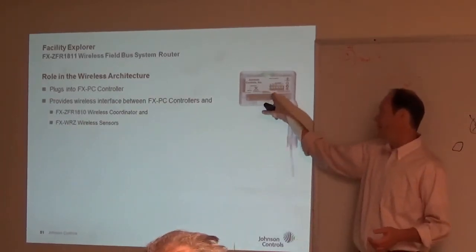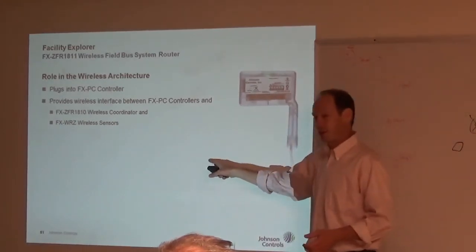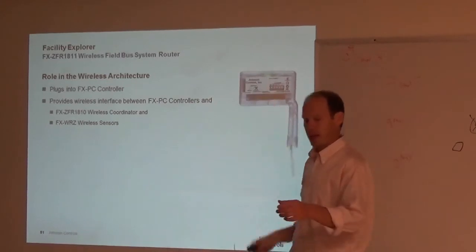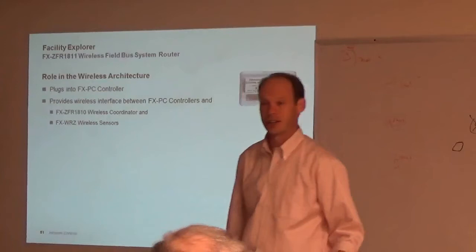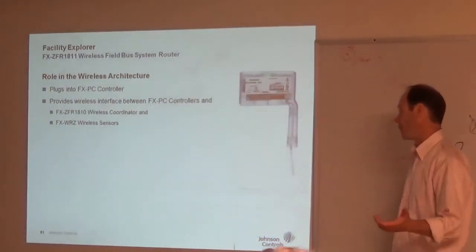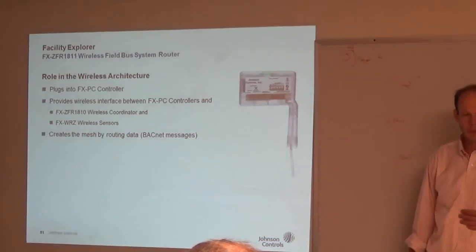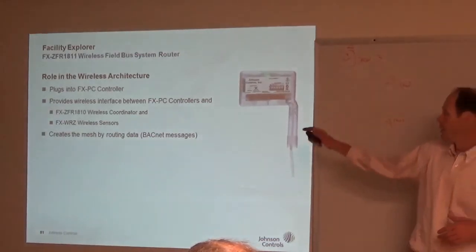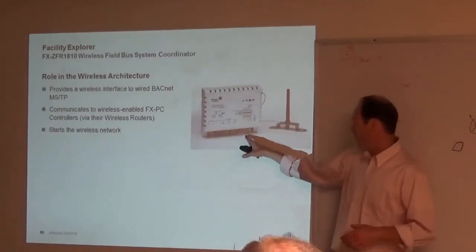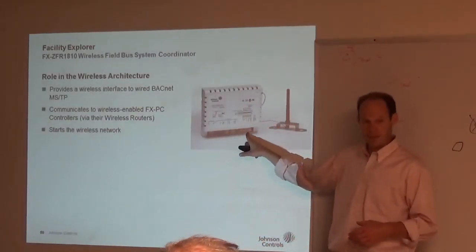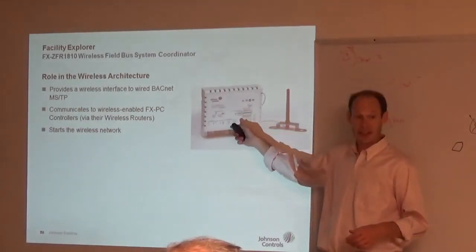And there's that dip switch right here, and that's my personal area network number. So the coordinator has a personal area network, the routers have a personal area network, and the sensors in the back, you put the personal area network on there so they know who I'm talking to, what controller, and what personal area network I'm on. So you just have to set everything on that the same. It's set on this guy right here, set on that one right there, and then everything else that talks to that has to follow suit. Correct. Everything that talks to this guy is in the same personal area network.